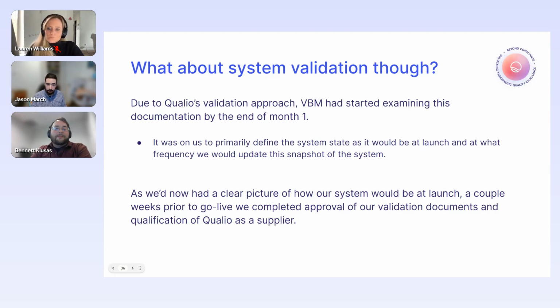FDA doesn't tell you how to validate your system. It tells you that you need to have a validated system, right? So it's how you approach the actual validation approach. And I mean, spot on. We had no shortage of skeptics over here about the validation approach. And once they dug into the documentation, there was nothing else for them to really say. They were like, yeah, wow, it's actually all here. Nothing really else to do, and we had a clear pathway.